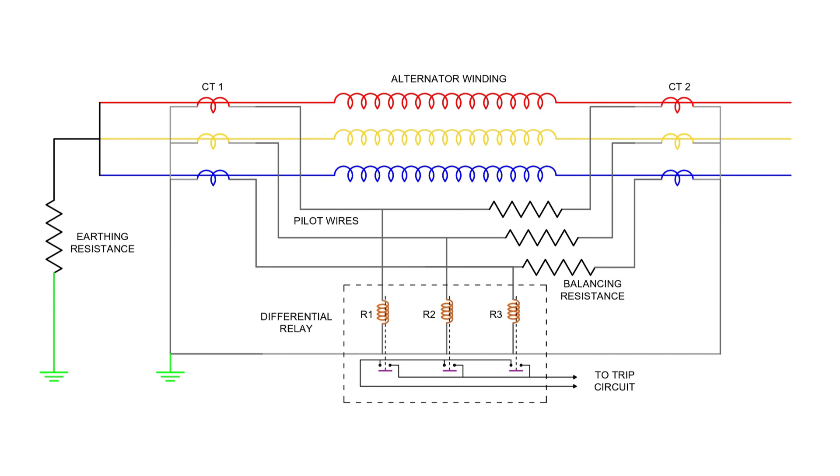To prevent this, balancing resistors are introduced into the circuit. These resistors are connected on the side with lower impedance to equalize the total resistance of both pilot cable paths. By ensuring that both CT secondary circuits face the same total impedance, balancing resistors maintain symmetry, reduce error current, and stabilize relay operation. This technique is essential in maintaining the reliability and accuracy of differential protection in real-world systems.